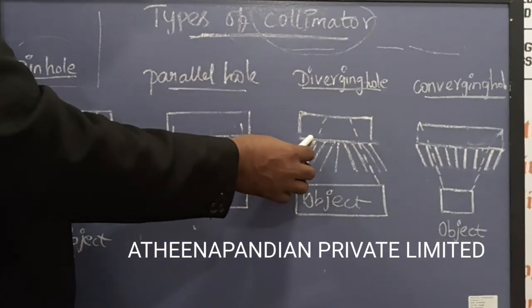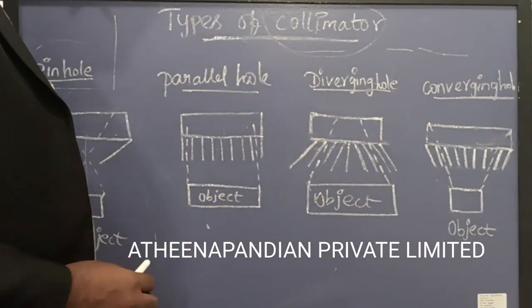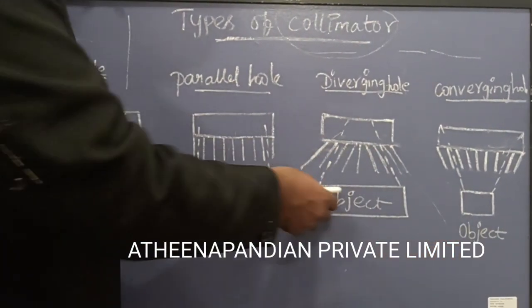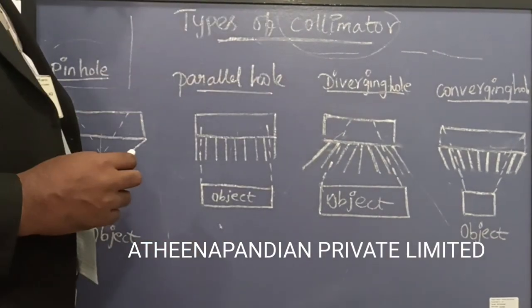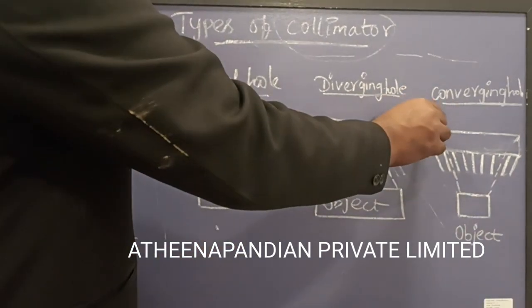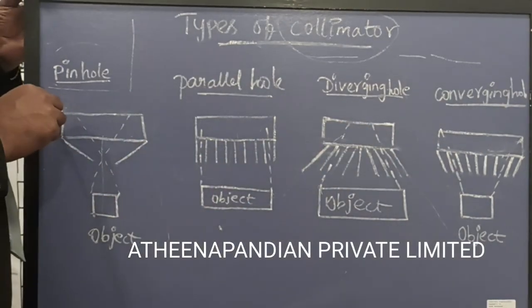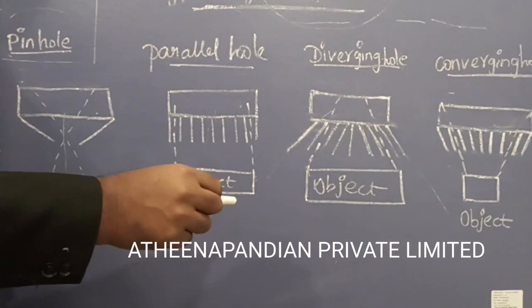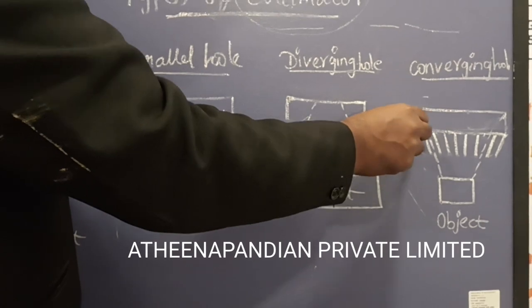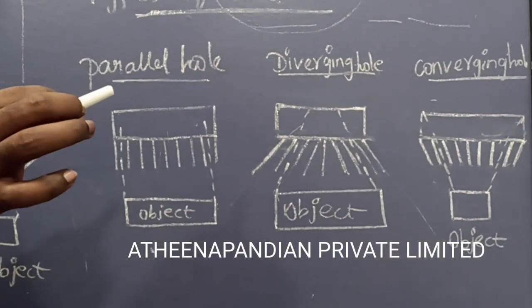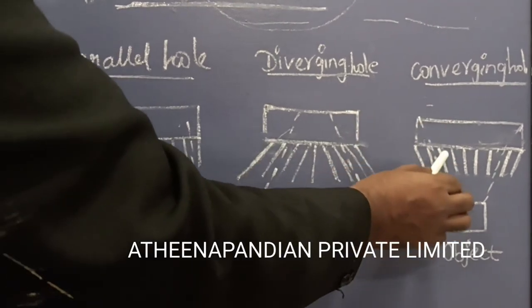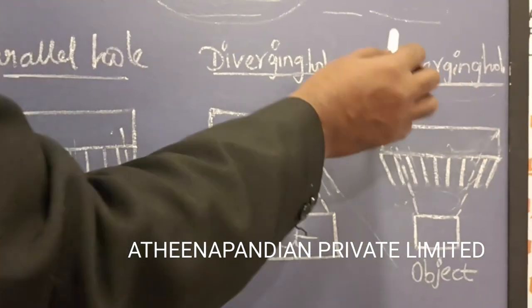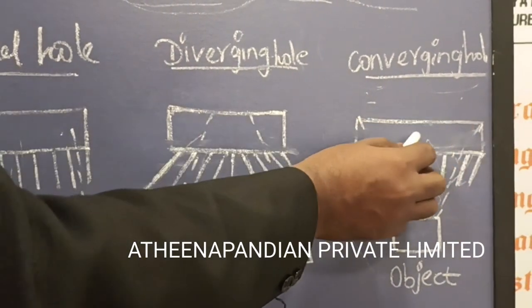For the divergent collimator, the holes are put in an inclined form, so you can spread the rays over the length of the object. If you want to cover a very broad area, then you can use this particular type. For the convergent collimator, the intensity of the X-ray will be large in a small area. All the intensity comes together in a single way. That's why, instead of the pinhole collimator, the convergent collimator is used when high focused intensity is needed.